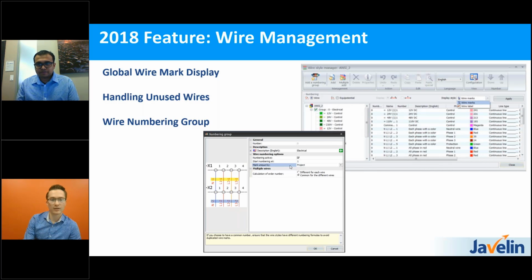Definitely. And it sounds like we have some new options as well for controlling how our wires are numbered. What is new in 2018 for that? So, as most of our customers know, and for the benefit of some of our new attendees today, you can sort your connections by groups. The groups could be electrical, hydraulic, pneumatic. It doesn't matter. You can create the group. But when you're tagging these connections or marks, you originally only had the option of doing it by project. Now you can do location, book, and also a file type. So you can make sure the marks are unique by any of those indicators.